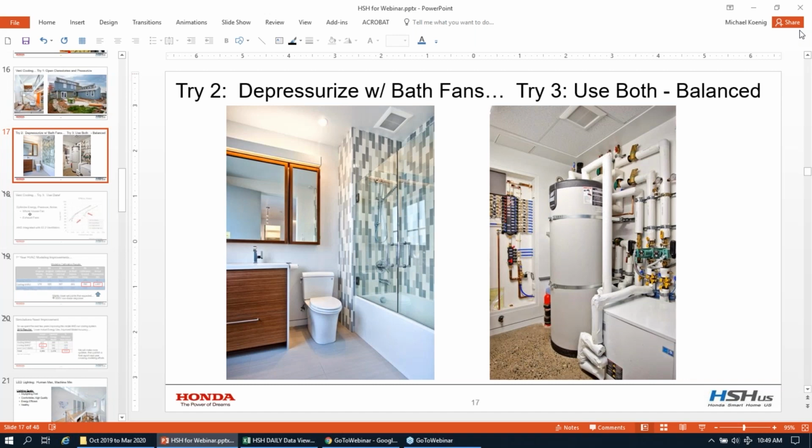But in retrospect, this is one of the things we should have done better. We did not actually create a hardware-in-the-loop simulation, which we should have done. We should have taken some of the HVAC hardware and properly vetted all the controls, because in my experience with this project, it was less about hardware limitations. It's this nice Bosch heat pump and these nice electric pumps, and all of these bits are individually sound. They're mass production products. It's the controls that are hard.